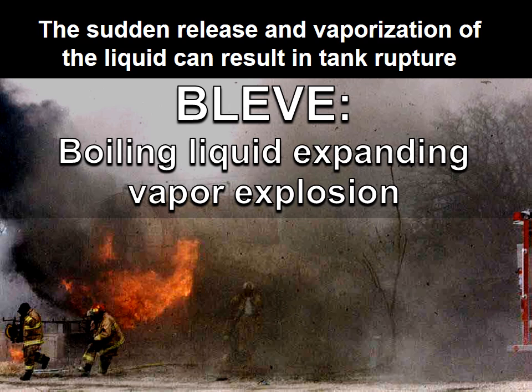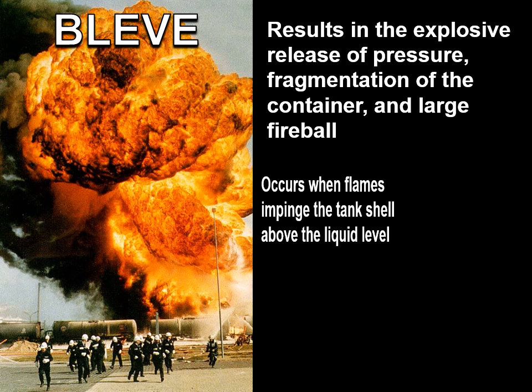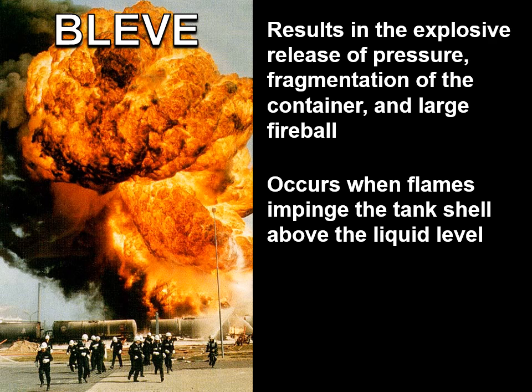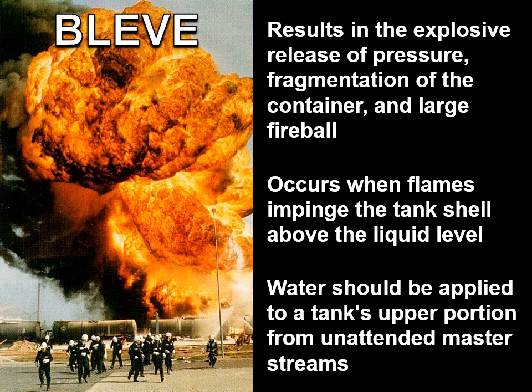This is called a BLEVE. It is boiling liquid expanding vapor explosion. It results in the explosive release of pressure, fragmentation of the container, and a large fireball. It occurs when flames impinge on the tank shell above the liquid level. Water should be applied to the tank's upper portion from unattended master streams.